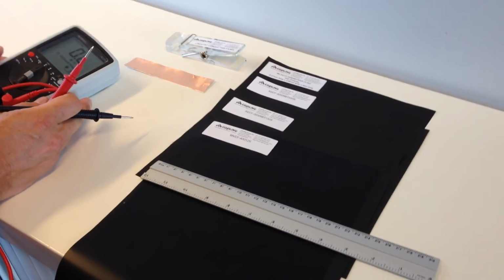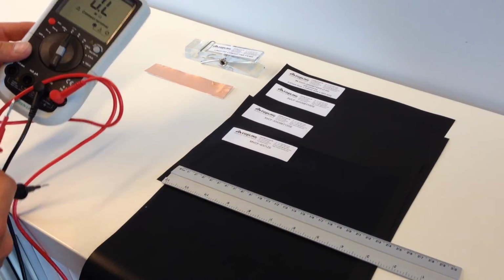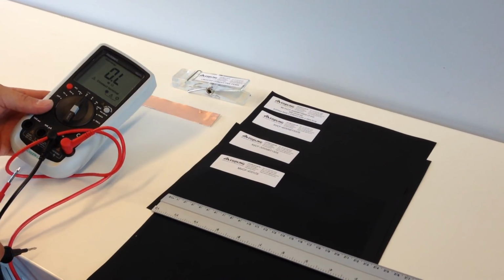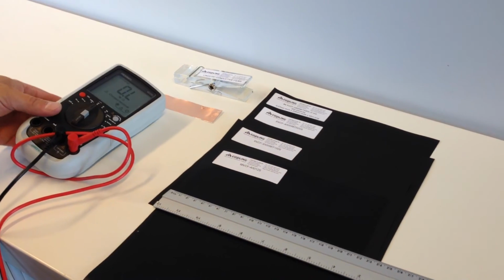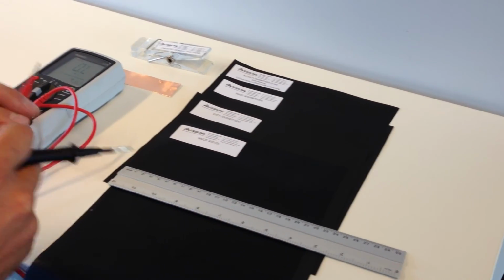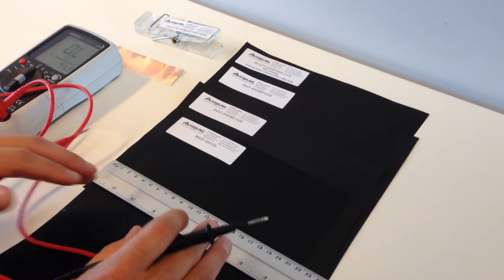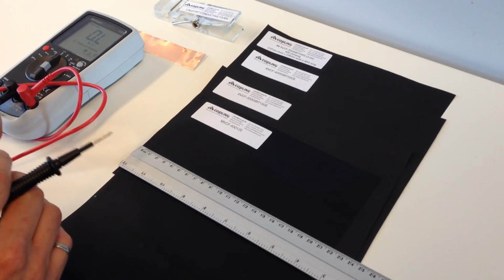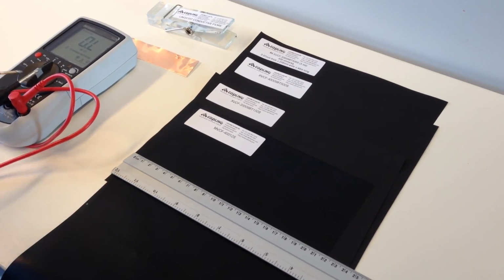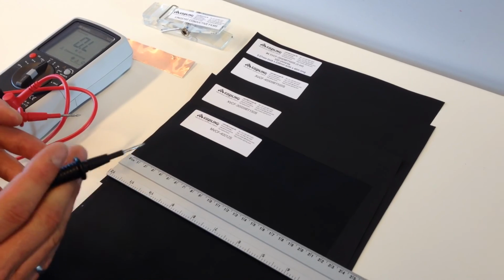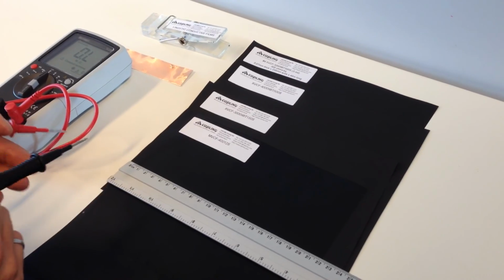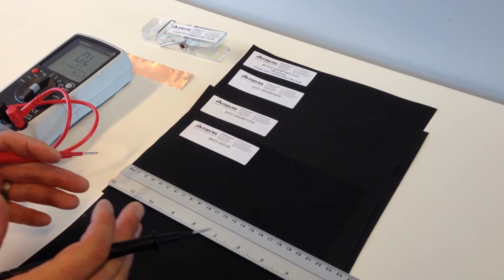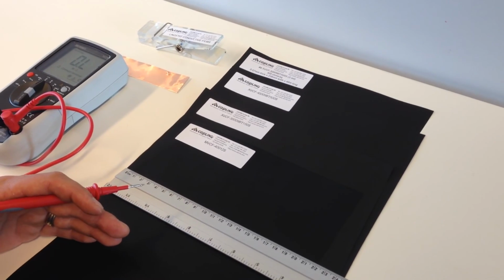The way that we measure it for the information on our data sheets and on our website is we just use a standard multimeter. The multimeter gives a value in ohms. The measurement that we have ultimately on the products is in ohms per square. Ohms per square is used for the surface resistivity because surface resistivity is supposed to be independent of the thickness of the material.